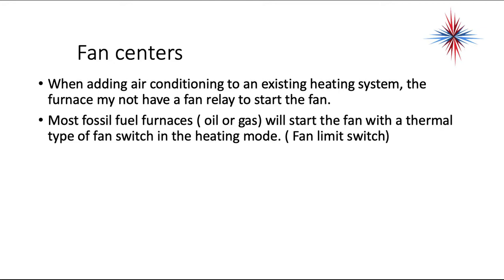But the problem is in air conditioning, if we didn't have a fan limit switch or fan center, we would never be able to start that fan motor running for air conditioning because the temperature doesn't go up. It goes down.